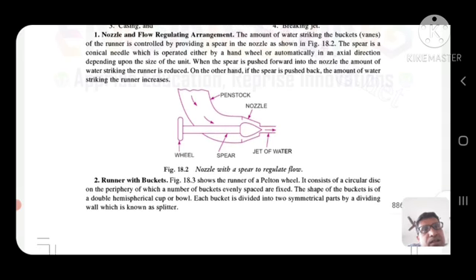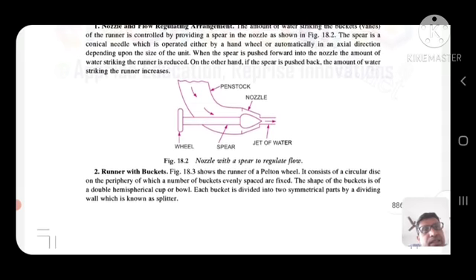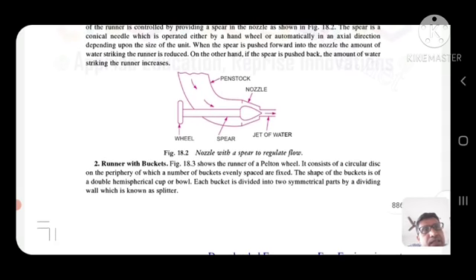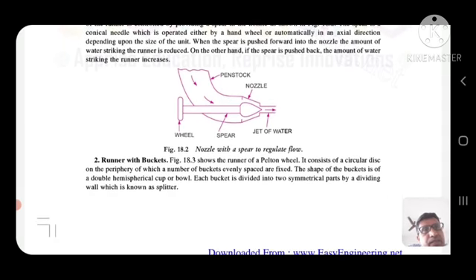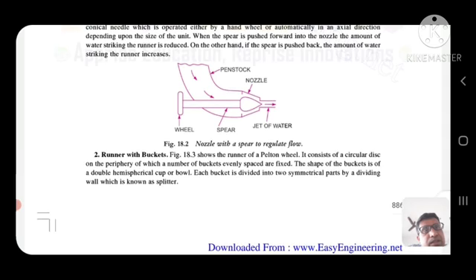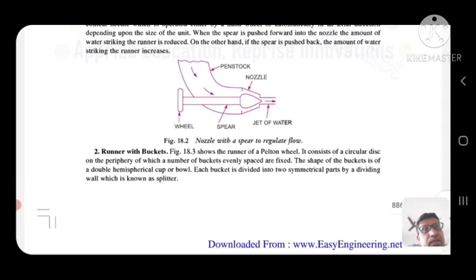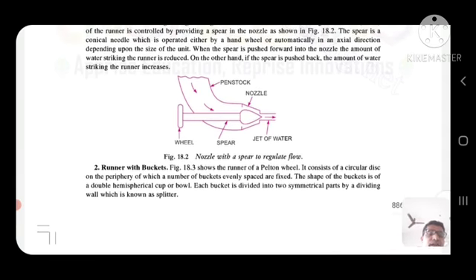Nozzle and flow regulating arrangement: the amount of water striking the buckets of the runner is controlled by providing a spear in the nozzle. The spear is a conical needle which is operated either by hand or automatically in an axial direction, depending upon the size of the unit. When the spear is pushed forward into the nozzle, the amount of water striking the runner is reduced; when the spear is pushed back, the amount of water striking the runner increases.